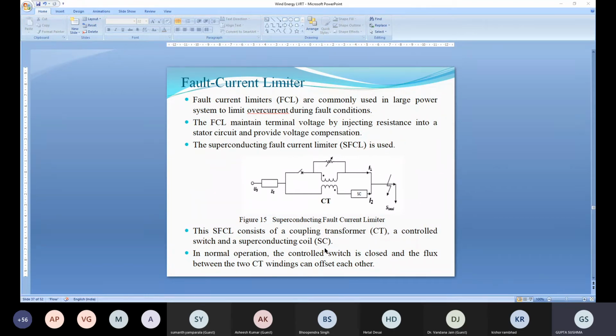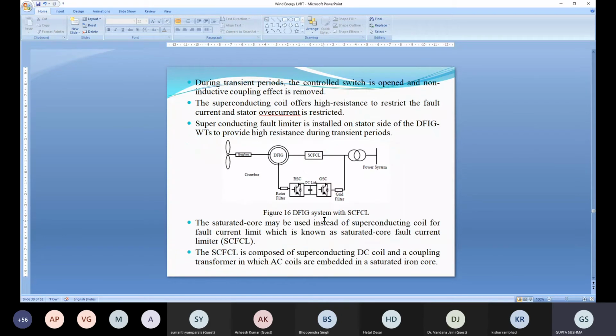So the superconducting coil offers high resistance to restrict the fault current, and the stator overcurrent will be restricted. Initially, the superconducting coil does not come into the picture, but as soon as a fault occurs, the superconducting coil offers high resistance and it will control the overcurrent. This is the circuit diagram. We connect the superconducting fault current limiter between the output of the DFIG and the grid.